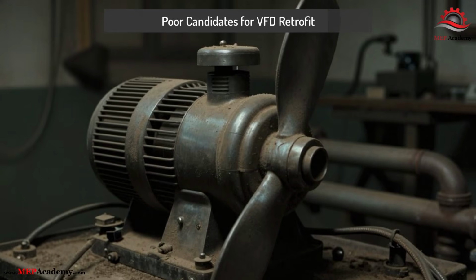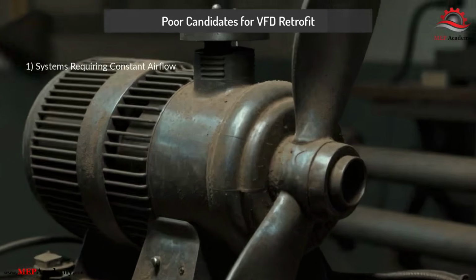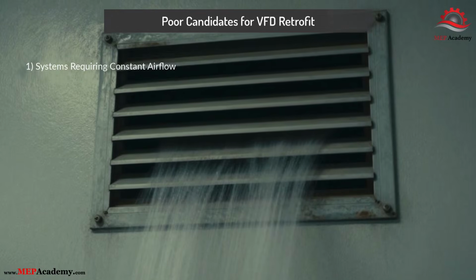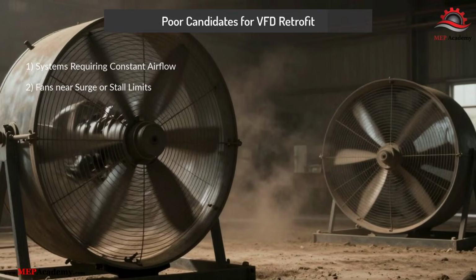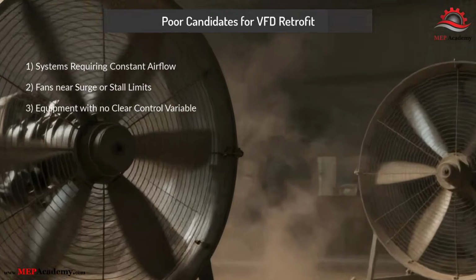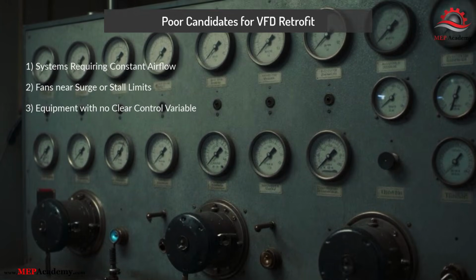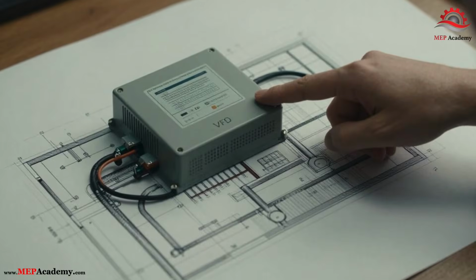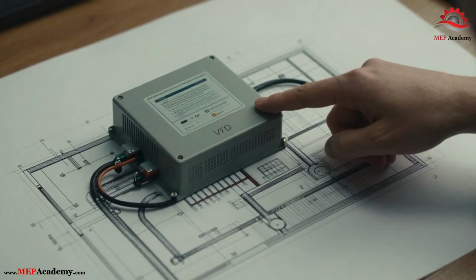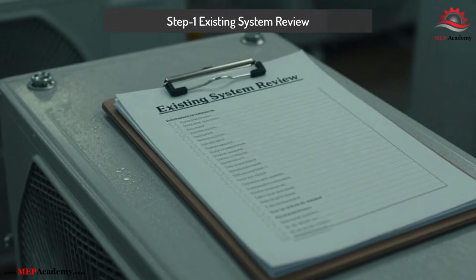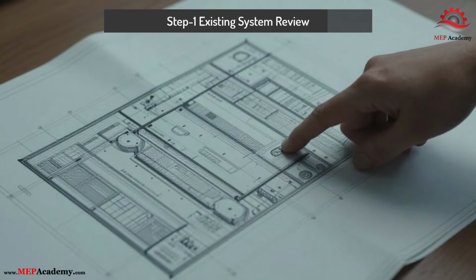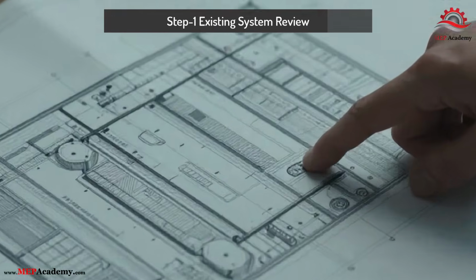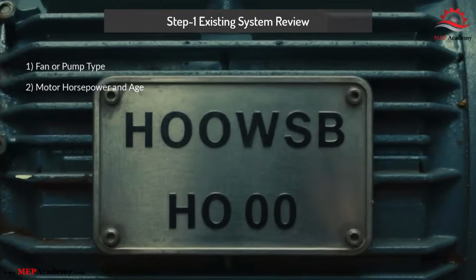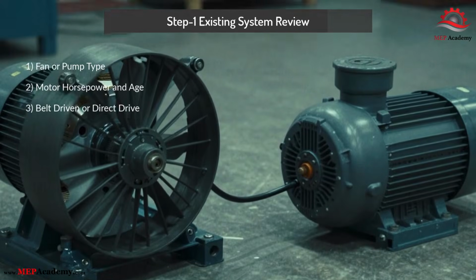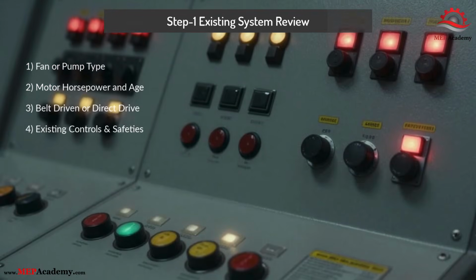Poor candidates for a VFD retrofit include systems with constant minimum airflow requirements, fans near surge or stall limits, equipment with no clear control variable. Section 3. The retrofit process. Drawing first. Step 1. Existing system review. Start by understanding what you have. Fan or pump type. Motor horsepower and age. Belt-driven or direct drive. Existing controls and safeties.